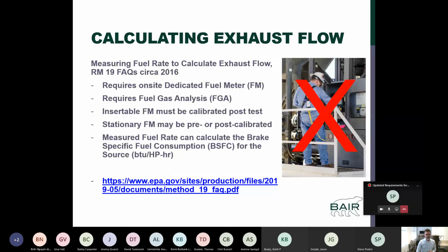So method 19 in the FAQ section, which I've got a link here at the bottom of this screen that you can directly access. What they came back and clarified was that if you're going to use method 19, you have to have a dedicated fuel meter per engine or per source that you are going to be testing on. A lot of compressor stations or gas facilities may have a master fuel meter where they know the total fuel usage for all of their sources at that station or that gas plant, but they can't divide it up per source. And so this was something that was changed.